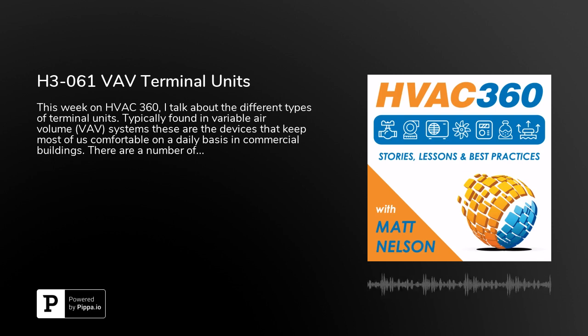As far as other things go, remember the box minimums. It's easy to say, when you go through your load calculations, it'll spit out a number and you say, okay, here's what you need for heating CFM. But when you actually go to the box manufacturer, they say, well, you know what, instead of 100, you have to go for this box size. The minimum flow is 150. There again, you're dealing with the question of what's the lowest value that the airflow measuring station can handle? So you have to be cognizant of that. If there's something that you want because the load calc says so, you have to make sure that the actual equipment matches up with that. So be cognizant of that.